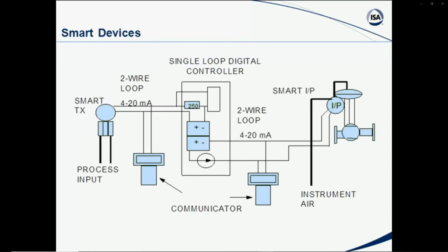As I said, sort of the same physical plant, we still have, in the case we're looking at here, some sort of a control function. In this case, we're showing a single loop digital controller. But the main thing that we've done here now, thanks to the microprocessors, is we can have a smart transmitter, or we can have a smart I/P or smart valve package.